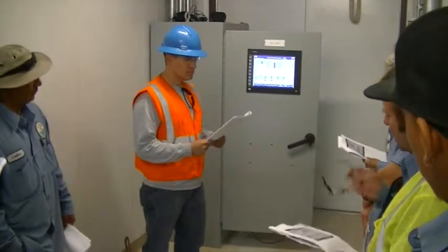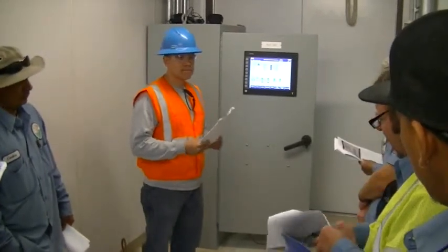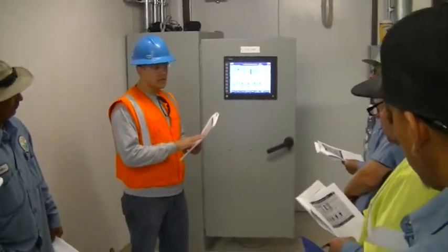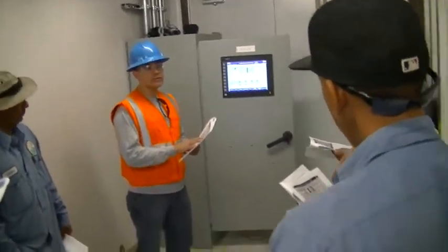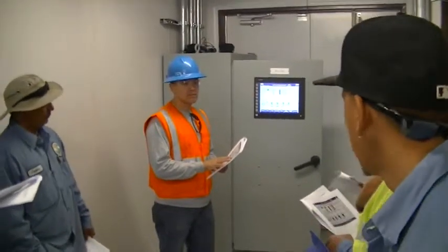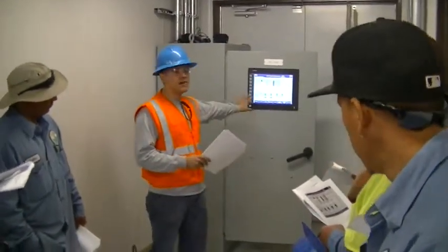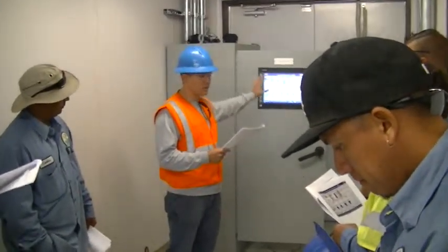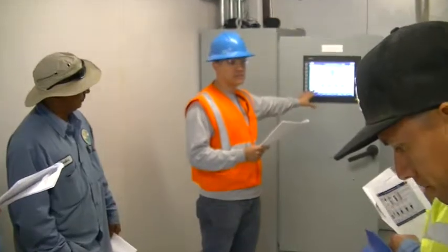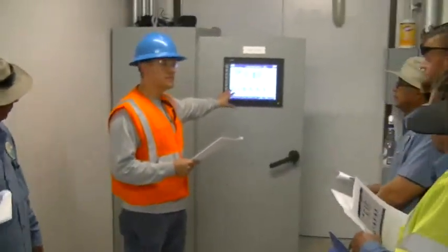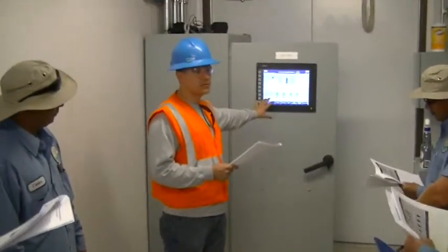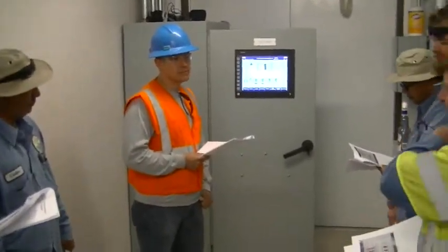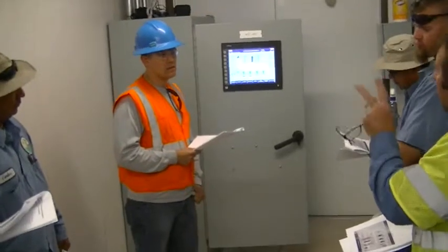Okay. And that doesn't actually lock the pumps out? That doesn't lock the pumps out, it puts it under control of the Mercoids. But it locks the PLC out from controlling anything at that point. So basically, if the PLC fails, or I lose that analog signal from my pressure, the PLC is locked out of control. It's not going to be controlled there anymore, it's going to go into control with the Mercoids. Right, so it'll work in auto operation, but it'll work off the Mercoids.